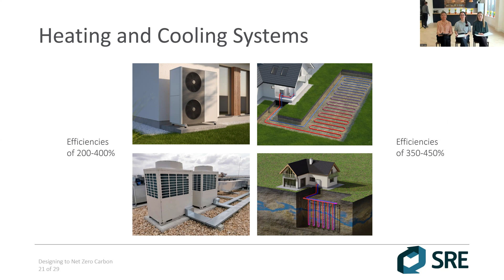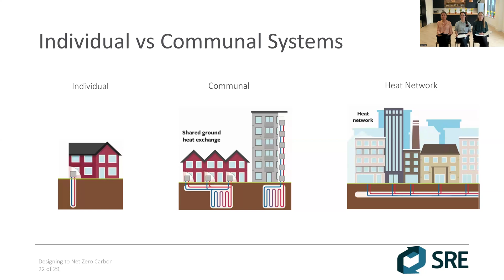There's often much discussion over the relative benefits of individual and communal systems. We're obviously talking about heating, cooling, hot water, and ventilation when we talk about these. Communal systems often are more energy efficient because they can benefit from economies of scale, and they're often easier to connect to district heating networks as well. However, there are drawbacks, and one of them is the long pipe runs. So again, we need to be thinking about minimising pipe runs and insulating pipe work wherever possible. There's also something that we have found, especially in a lot of the student accommodation that we've worked with, or care homes, that a lot of the communal areas where the pipe runs go do suffer from overheating. So again, that's something that might be considered a drawback of communal heating systems.